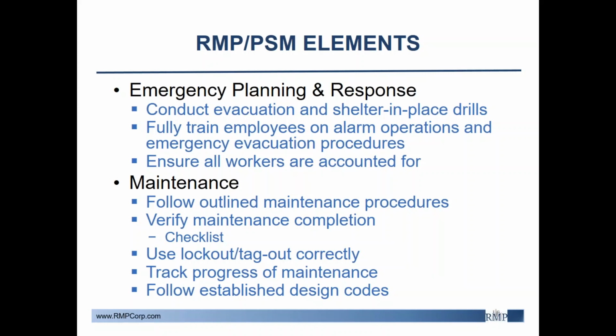The other key prevention program element to address is maintenance. This accident was caused by a miscommunication between operators and a lack of proper maintenance documentation and checklists. Lockout-tagout procedures were not followed, and no required maintenance authorization signatures for the start or completion of the maintenance were obtained. ASME Boiler and Pressure Vessel Code, Section 8, requires that when a pressure relief device is temporarily blocked and there's a possibility of vessel pressurization above the design limit, a worker capable of releasing the pressure must continuously monitor the vessel.